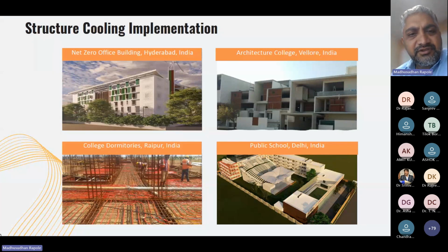But the uniqueness of this building is we are achieving net zero with the solar plant installed on the rooftop alone. No outside power is being wheeled in to achieve net zero. That's why this is a very unique building in the world. The reason we've been able to achieve this is, of course, the building design and architecture all matter, but one of the main reasons is we are able to use structure cooling here, because with structure cooling I end up using only 0.05 kilowatt per ton compared to 1.2, 1.5, 1.6.